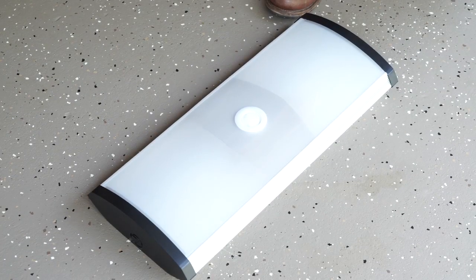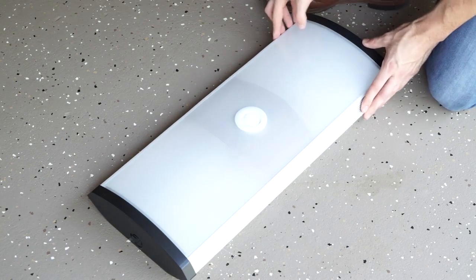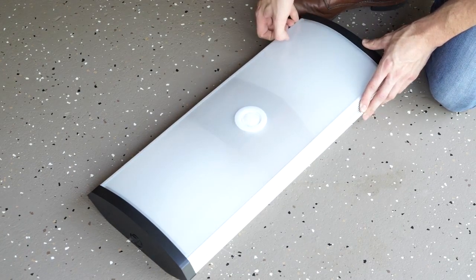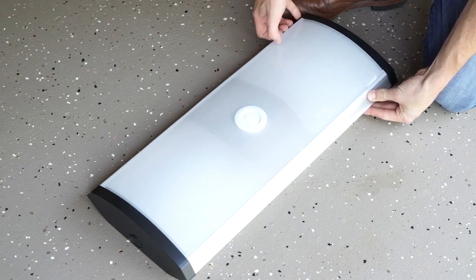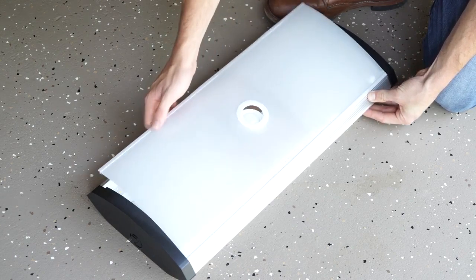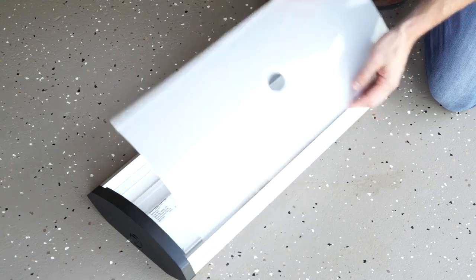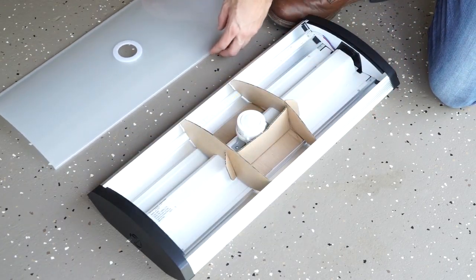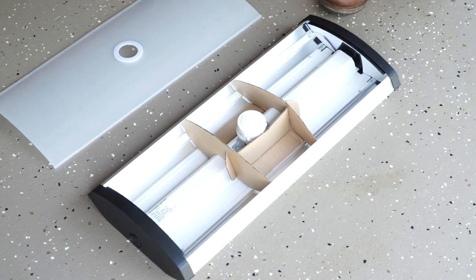First, we want to remove the diffuser and adjust the PIR sensor to the desired settings. Remove the diffuser from the housing by grasping the edge of the diffuser near one end of the housing. Carefully squeeze the diffuser to release it from the housing, and then continue down the length of the diffuser to fully disengage.